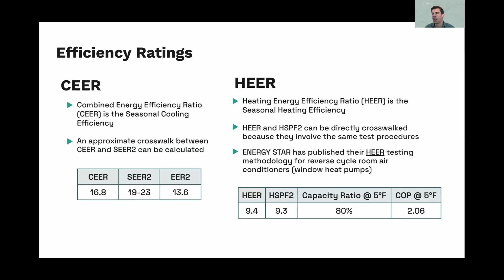Here's an example spec sheet. The important thing to call out is the capacity and the COP at lower temperatures. In a place like New York City, 17°F might often be the design temperature, so they're looking at what the capacity is at 17°F and whether it can meet the building's needs.